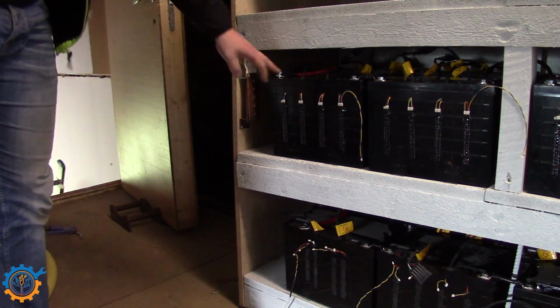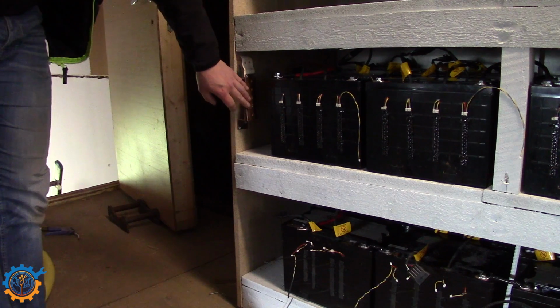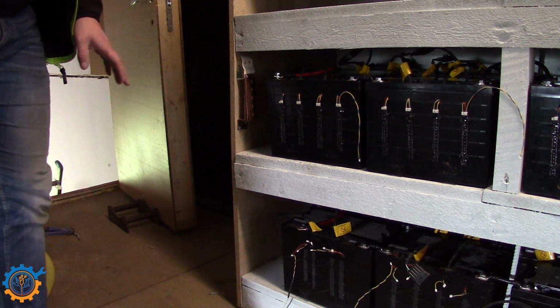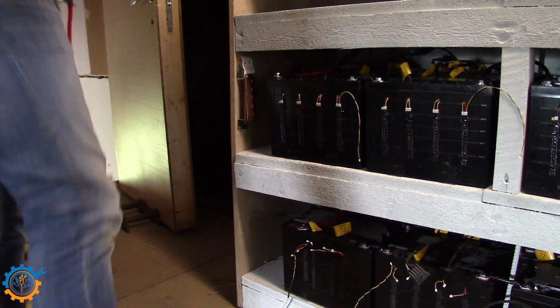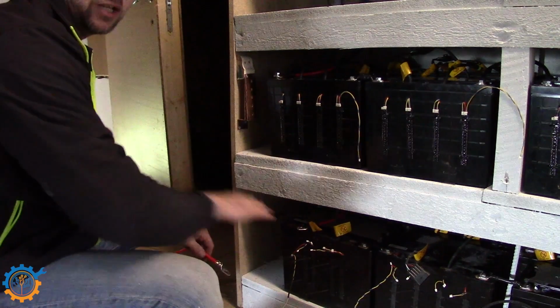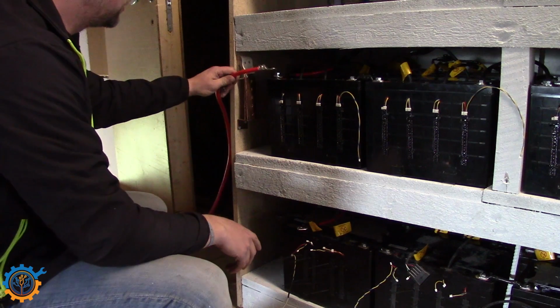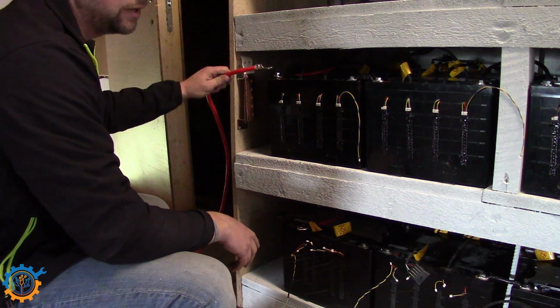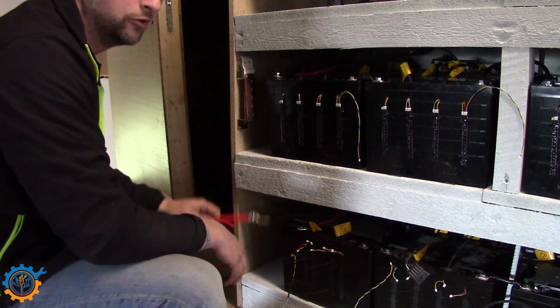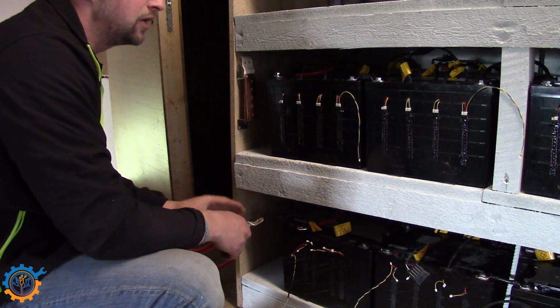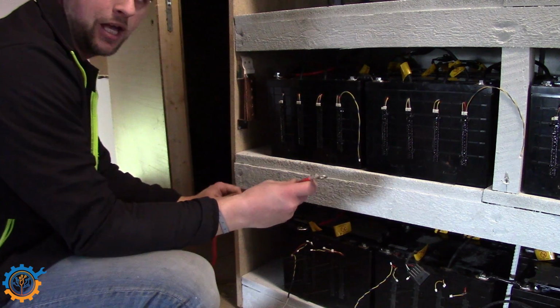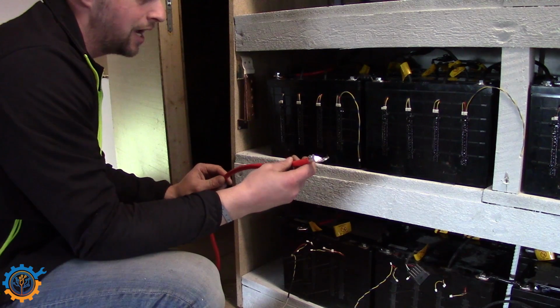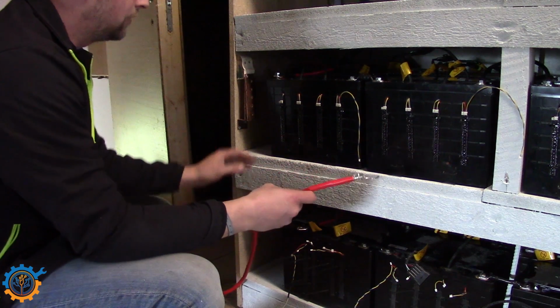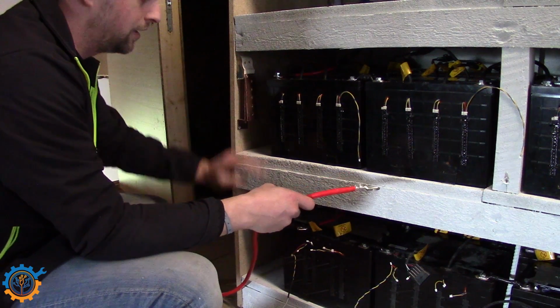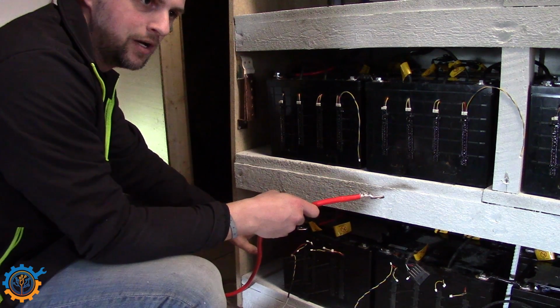Next part is to wire the batteries up to the terminal here that goes down to the inverter. What's important is to make sure you use the same type of wire and the same length for all the strings. So even though this one may be short, you should use the same distance of wire as the other one if you want it to be 100% even. This is especially important if you have voltage drop in the cables and don't have really thick cables, because it could pull more current from one string than another due to the voltage drop.